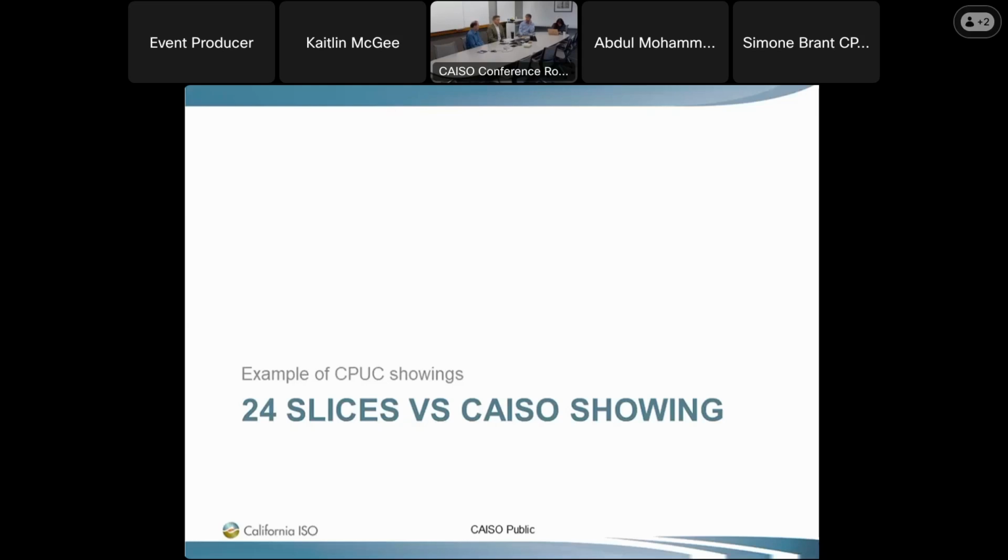Okay, so it's not just for solar, and for batteries this necessarily wouldn't apply because of what we were discussing earlier, that the CAISO will just receive the total NQC divided by the number of hours for that battery. So even if the battery doesn't appear in this peak hour, the CAISO won't receive the 0.1 megawatt QC value. They'll still receive the NQC divided by hours. Right, the NQC for the storage won't change. It doesn't make a difference which hours you show it for on the slice of day show. Okay, and so the 0.1 megawatt is for any other resource that doesn't appear in the peak hour but does appear in that 24-hour profile. Yes, what it applies to is the resources that have a 24-hour profile, which are the 3 I just said: solar, wind, and DR. Okay, great, thank you.